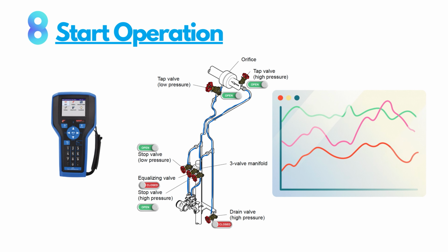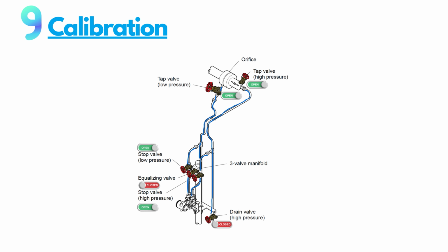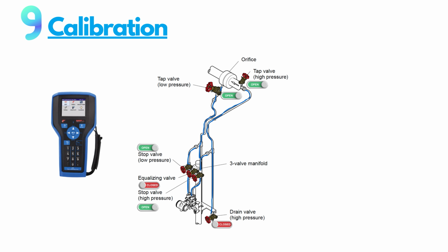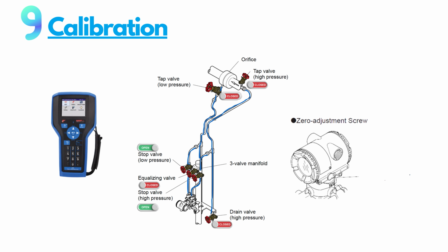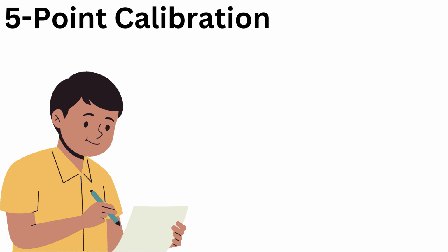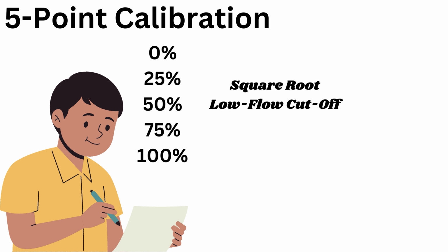Step 9. Calibration of transmitter. Once installed, it's time to calibrate your transmitter. Calibration ensures accuracy in measurements. Here's how to do it. Start by zeroing the transmitter. Isolate the transmitter from the process, then apply zero pressure. Adjust the zero setting until the output reads 0. Apply reference pressures of 0%, 25%, 50%, 75% and 100% of the measurement range to the transmitter.